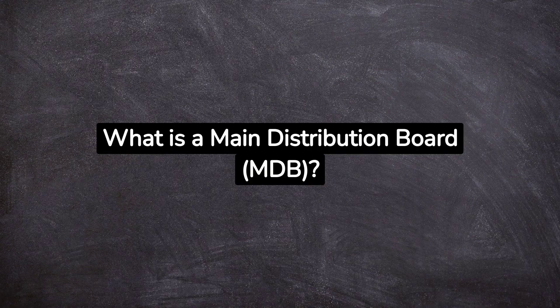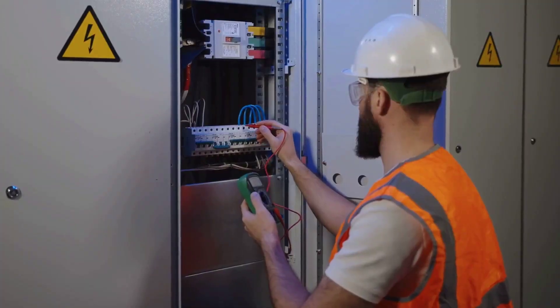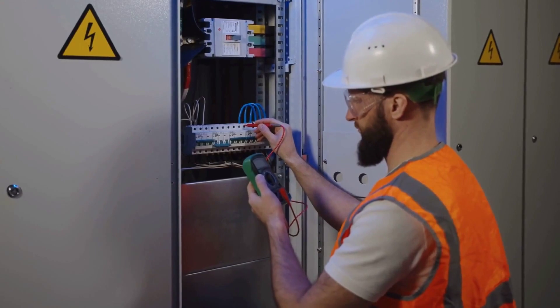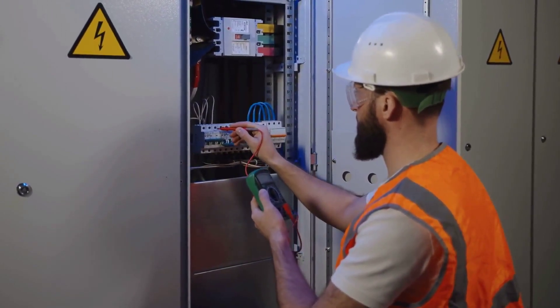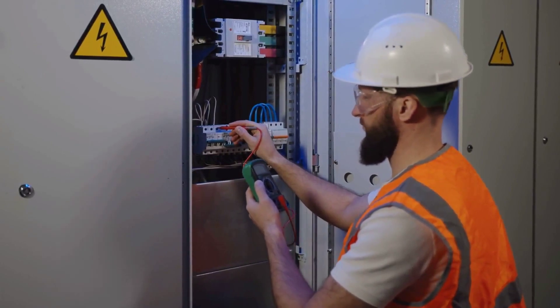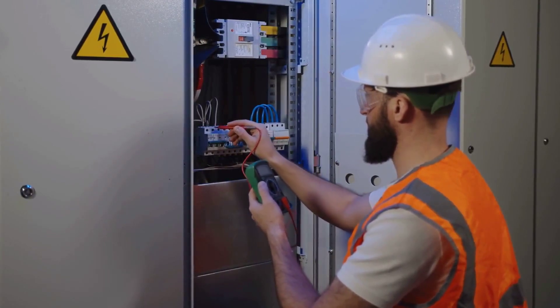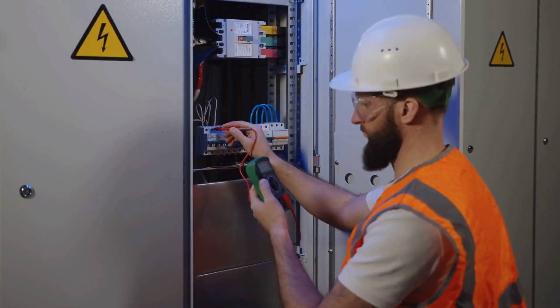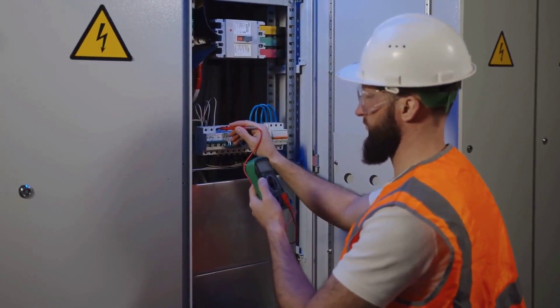What is a Main Distribution Board (MDB)? The Main Distribution Board, MDB, is a distribution board that fulfills all the functions of a main electrical distribution for the supplied area assigned to it, and where the voltage is measured for operating the electric supply system for safety services. The MDB is a low-voltage switchgear installed in a building or its detached part, used to distribute electrical energy between the distribution and final circuits connected to it. By means of the switchgear, control gear, and protective equipment installed in the MDB, the electrical circuits connected to it are protected and controlled. The MDB will also normally provide a main switch, known as an incomer, which switches the phase and neutral lines for the whole supply.